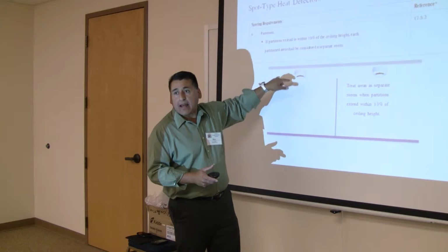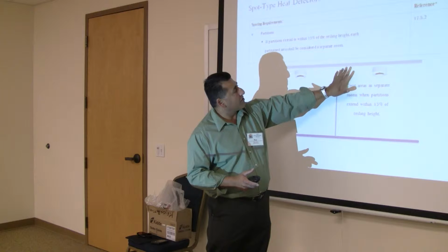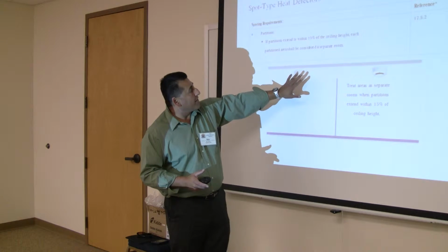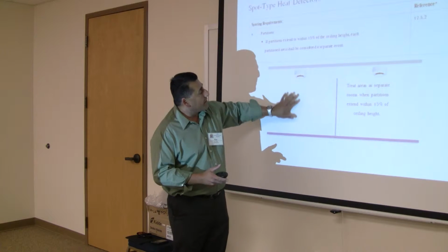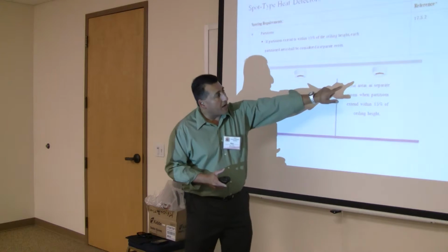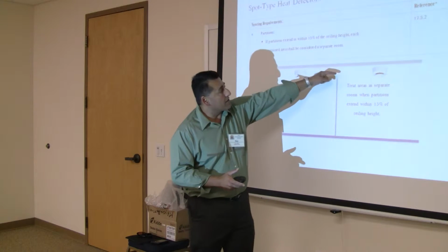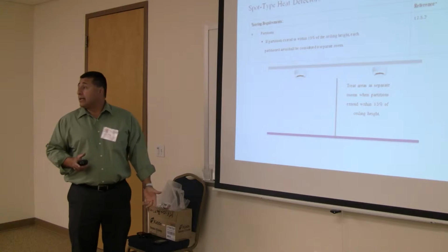side. You have to add another detector on the opposite side. Because what happens is the smoke actually travels up, banks over, and kind of stays in that area. So if you end up having an issue over here and don't put that in there, what's going to happen is this area is going to be not covered. You can't cover it with that detector because it's going to stay here until it gets so overwhelmed that it's going to start bleeding through, and by that time it's too late, right? You want to get early detection on that stuff.